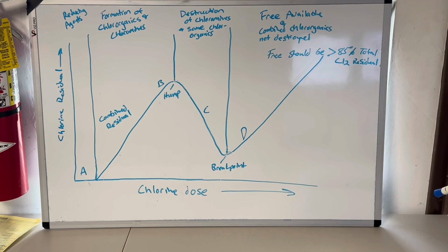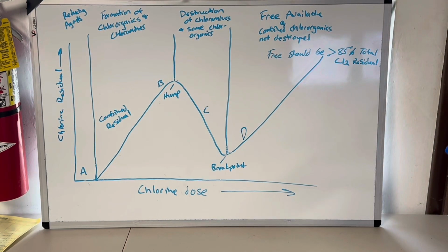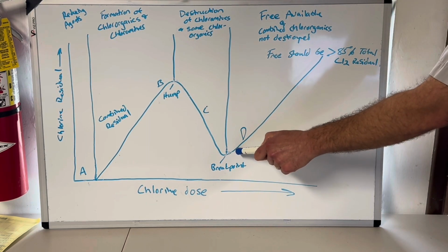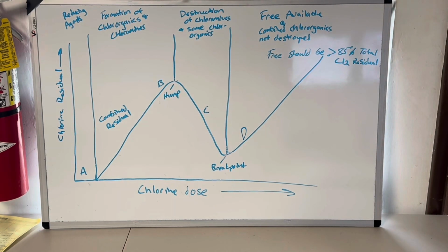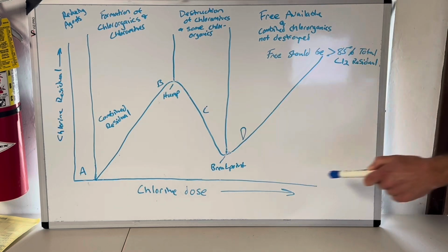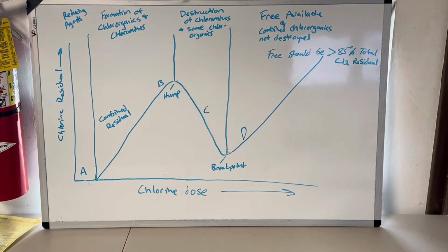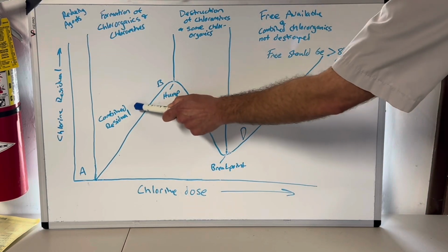So when both of my processes are running in parallel, I use a combined residual to disinfect because oxidizing the ammonia is impractical from a financial standpoint. And I have enough contact time in my contact chamber to effectively disinfect. I have to run a higher residual here because it's a weaker disinfectant than free available, quite a bit weaker. But it's effective, so long as my turbidity is in a decent spot.